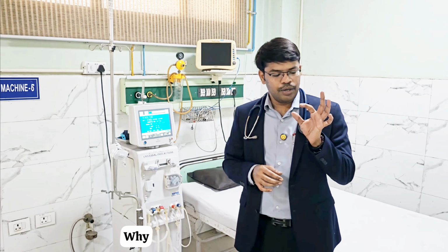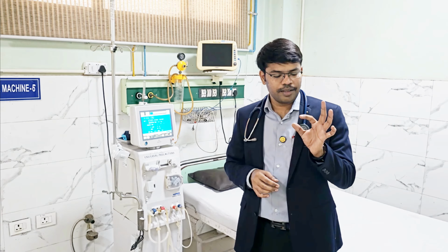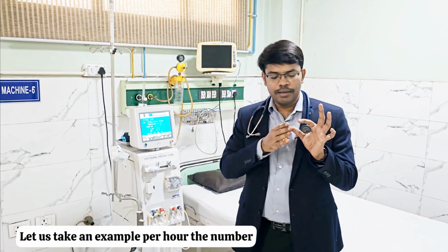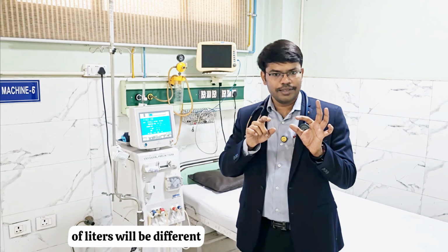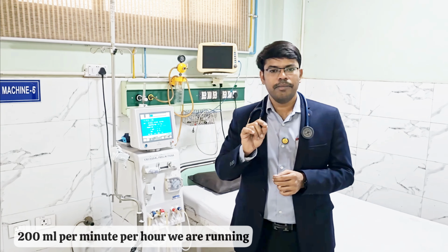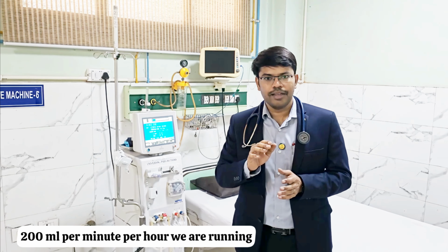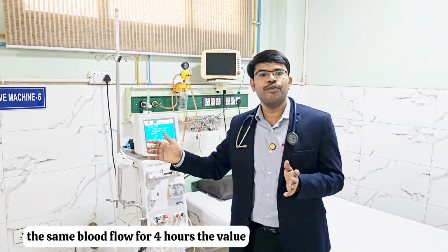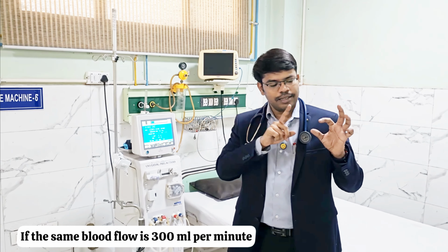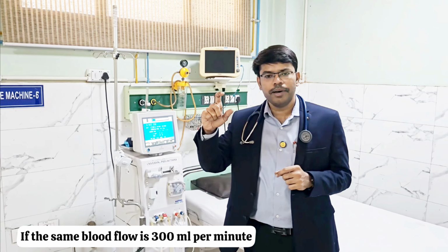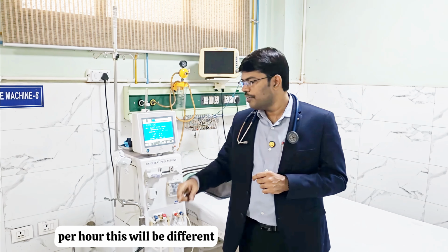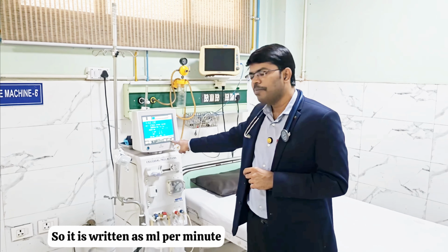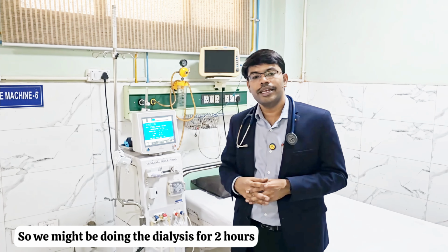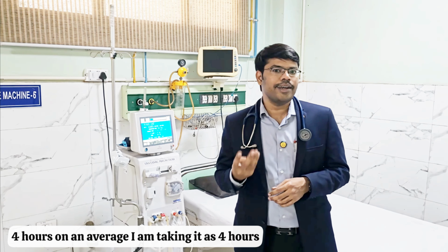Why? Let us take an example, 200 ml per minute. Per hour, the number of liters will be different. 200 ml per minute, per hour. If we run the same blood flow for 4 hours, the value will come different. If the same blood flow is 300 ml per minute, per hour, this will be different. So it is written as ml per minute. We might be doing the dialysis for 2 hours, 4 hours. On an average, I am taking it as 4 hours.